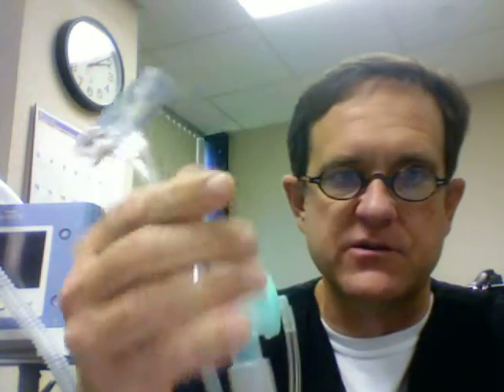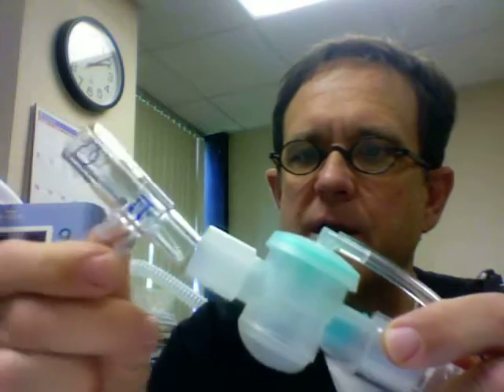And of course it has the line that you can hook up to a spot on the ventilator to work the exhalation valve. And then finally there's one more modification that can be added to that, and that is a flow sensor that can be put in line. And that would be put right here, and then this end connected to the adapter, which then connects to the patient's airway.